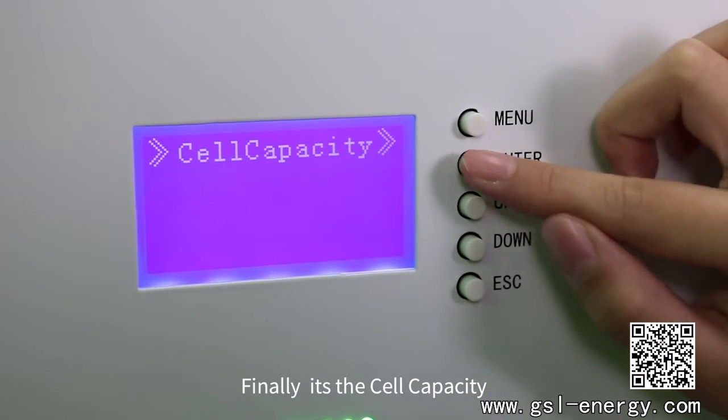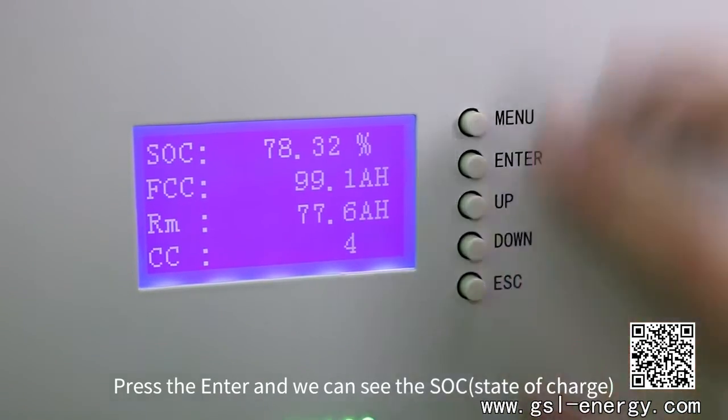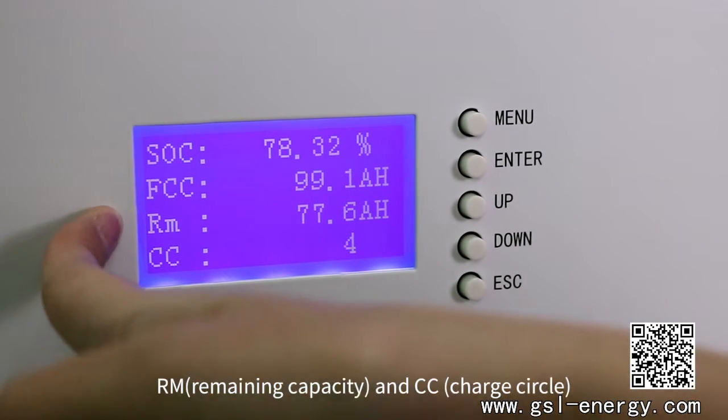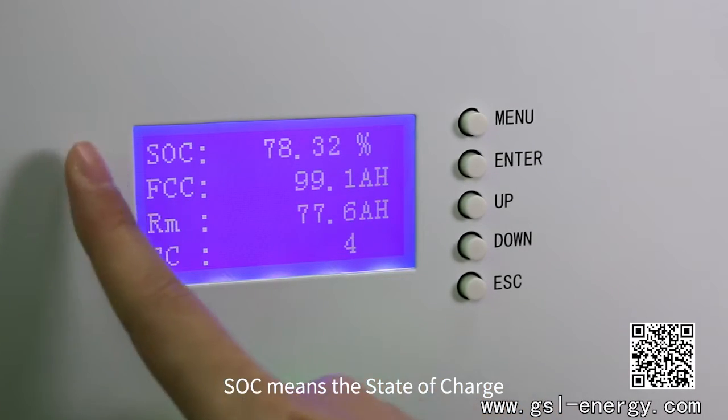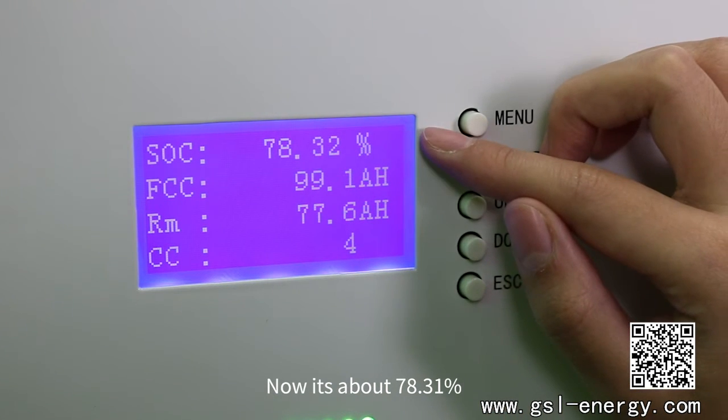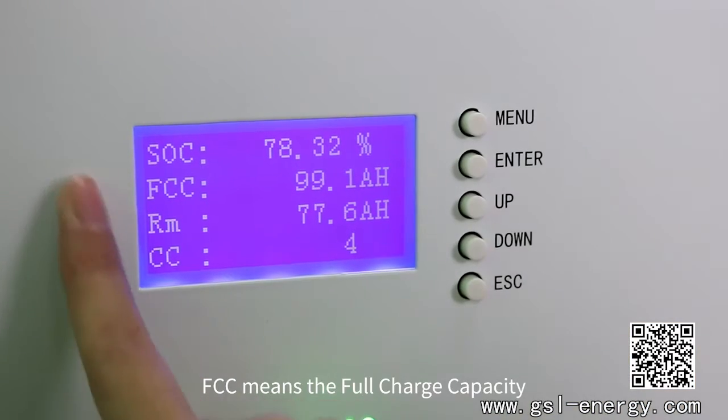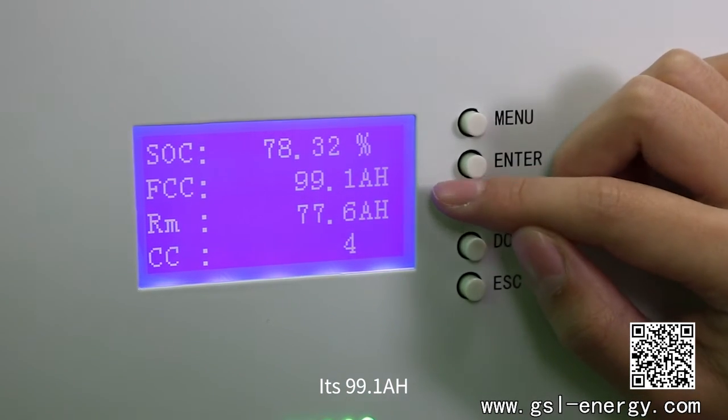Finally is the cell capacity. Press the enter and we can see the SOC, FCC, RM, and CC. SOC means the state of charge, now is about 78.31%. FCC means the full charge capacity is 99.1 amp hour.